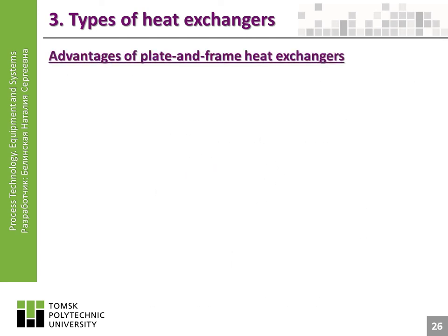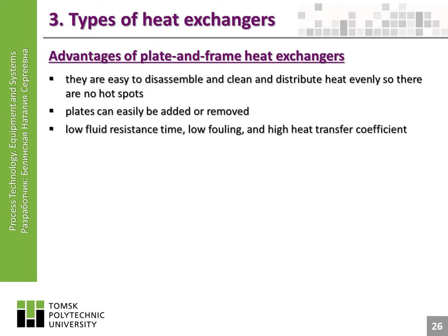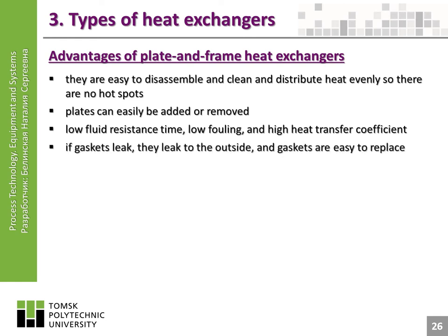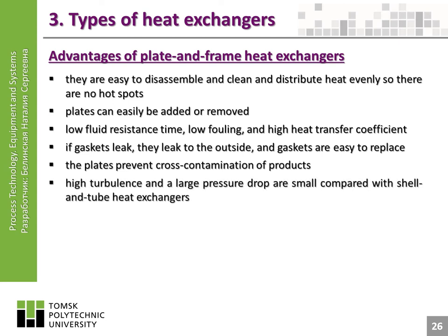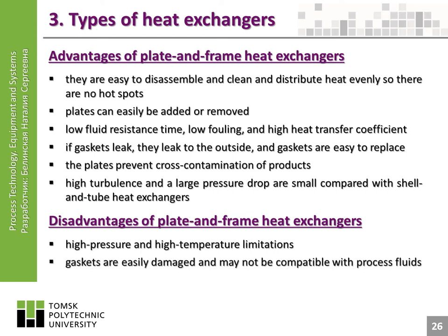Advantages of plate and frame heat exchangers: they are easy to disassemble and clean and distribute heat evenly so there are no hot spots. Plates can easily be added or removed. They have low fluid resistance time, low fouling, and high heat transfer coefficient. If gaskets leak, they leak to the outside, and gaskets are easy to replace. The plates prevent cross-contamination of products. High turbulence and a large pressure drop are small compared with shell and tube heat exchangers. Disadvantages include high pressure and high temperature limitations, and gaskets that are easily damaged and may not be compatible with process fluids.